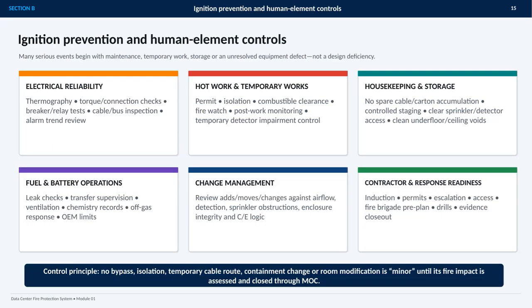This section focuses on ignition prevention and the human element controls that keep small issues from becoming serious events. Many incidents begin during maintenance, temporary work, storage, or an unresolved equipment defect, rather than from a deficiency in the original design. The central principle is that no change is minor until its fire impact has been assessed and formally closed through management of change.